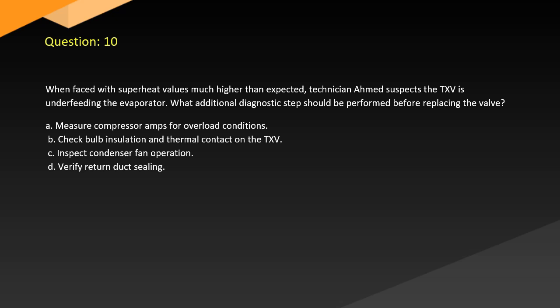Question 10. When faced with superheat values much higher than expected, technician Ahmed suspects the TXV is underfeeding the evaporator. What additional diagnostic steps should be performed before replacing the valve? A. Measure compressor amps for overload conditions. B. Check bulb insulation and thermal contact on the TXV. C. Inspect condenser fan operation. D. Verify return duct sealing.